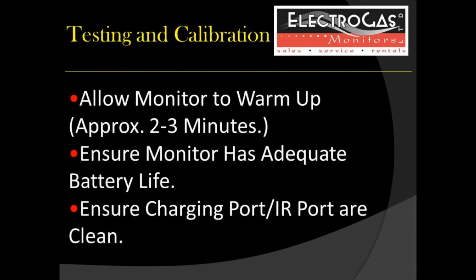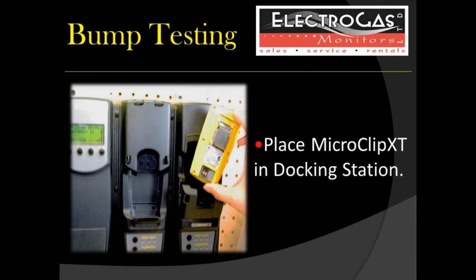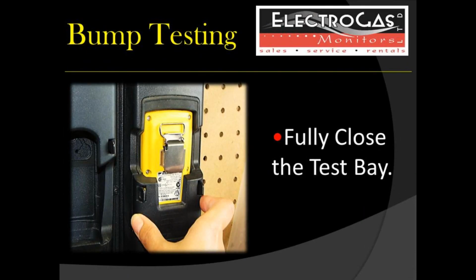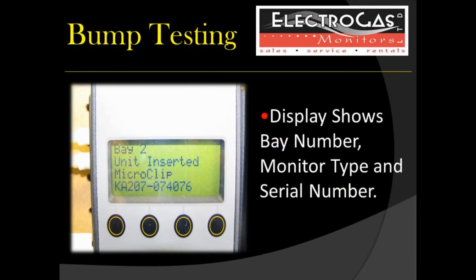Before you begin, allow your monitor to warm up for 2 to 3 minutes. Ensure your battery is adequately charged and that your charging and IR port is clean. Place the unit into the station face down. Next, fully close the test bay. The display on your docking station will show the bay number, the monitor type, and the serial number of the unit.